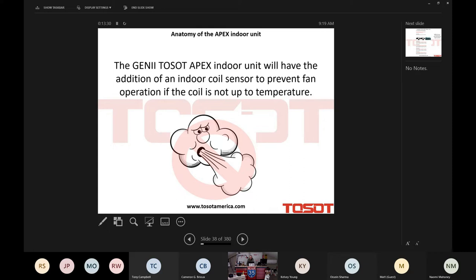So the Gen 2 Tosot Apex indoor unit, guys, which we are already up to the Gen 2, or it is forthcoming. I actually think you guys, Emco, has some already, which is wonderful. But you'll notice that the indoor unit will have the addition of an indoor coil temperature sensor to prevent fan operation if the coil is not up to temperature. Now, how we're accomplishing that right now with the Gen 1 is frankly through a delay fan setting on the thermostat. Virtually all the digital thermostats nowadays, even the less expensive ones, like you'll see the one that I use.